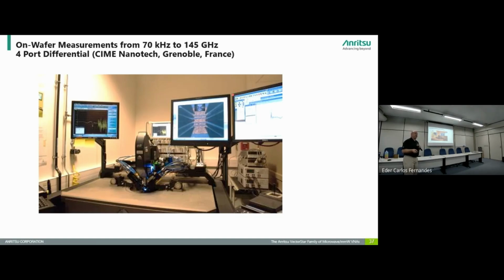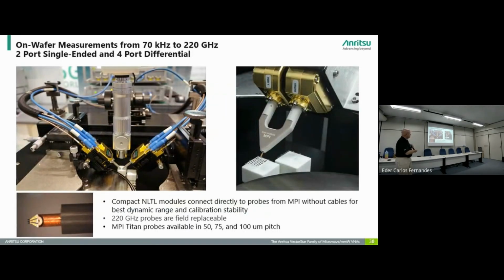The reason why we partner with MPI is because of the probe. MPI brings the only probe that we can use to 220 gigahertz in a single sweep. But this is just the surface here. This probe station actually has legs and everything all built in to absorb the vibration. But the smaller probe stations, the manual ones, you'd want to put on a certain vibration table so that they're properly isolated from any movements in the room. This one is so large it goes to the floor, and all the shock absorption is built in. But that's a 300 millimeter prober. These others that I showed are smaller, so they're going to be on some kind of vibration table.